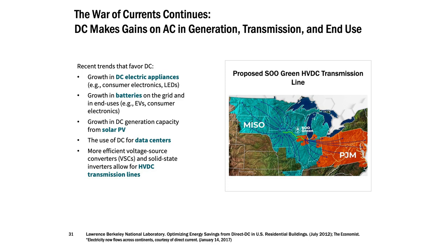These HVDC lines have greater efficiency in terms of lower line losses. But one of the challenges is that you have to convert the AC to DC in order to use those HVDC lines, and then back to AC again, which creates losses as well. So it's really an optimization equation where you have to make sure your HVDC line is long enough that the efficiency gains of transmitting over DC justify the efficiency losses of converting AC to DC and back again.